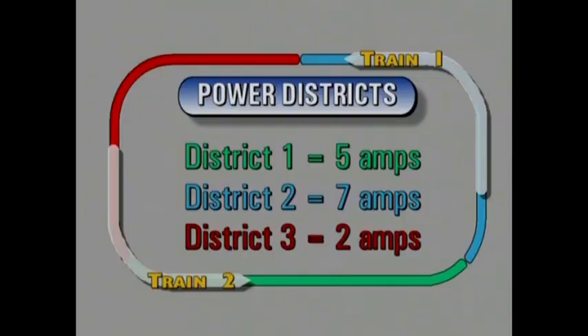If we move each train ahead another half train length, we'll have this scenario: train number 1 is now all in District 2, so transformer number 2 has to deliver 7 amps. The head end of train number 2 has moved into District 1, increasing the load on transformer number 1 to 5 amps. The rear 5 cars of train number 2 are still in District 3, so the load on transformer 3 has dropped to only 2 amps.